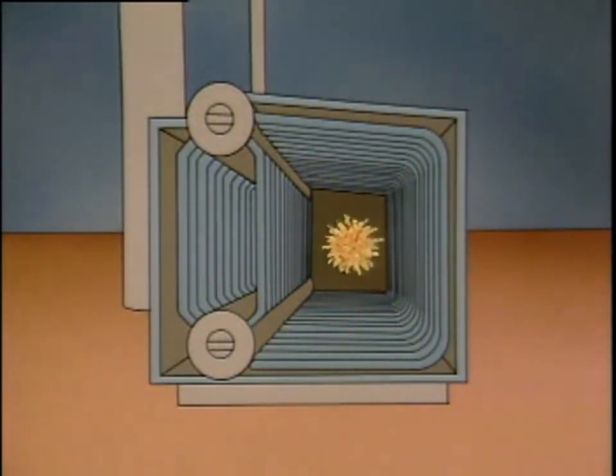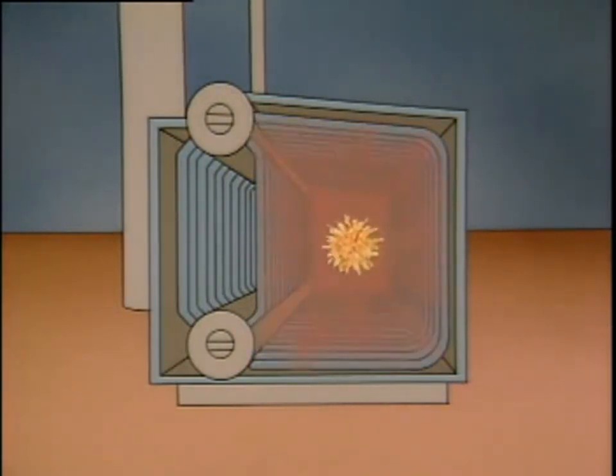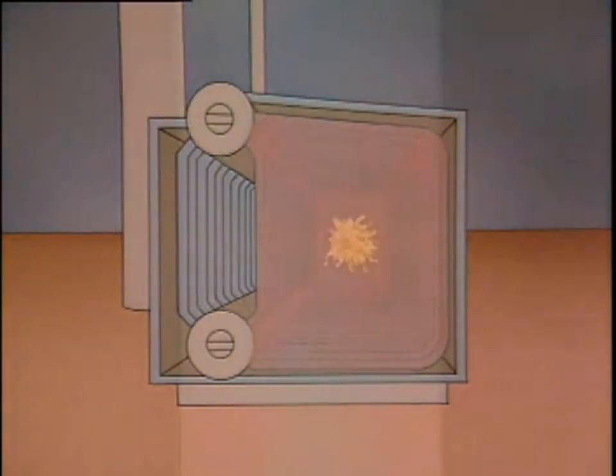The burning fuel also produces combustion gases. As these hot gases pass through the boiler, they transfer heat to the tubes as well. This is convection heat transfer. As the outer surfaces of the tubes absorb heat, conduction heat transfer occurs. Heat is transferred from the outer surface to the cooler inner surface, then from the inner surface to the water flowing through the tube. Convection heat transfer also occurs as the warmer water mixes with cooler water. When enough heat has been transferred to raise the water temperature to the boiling point, steam is produced.